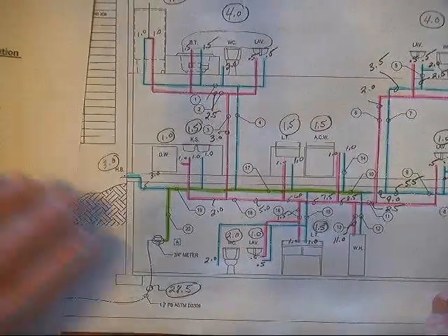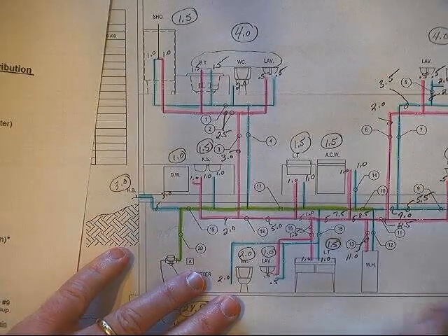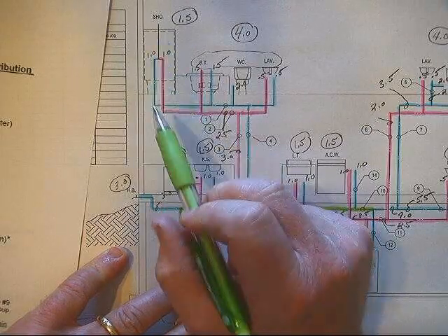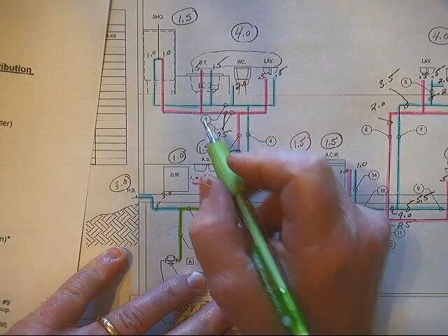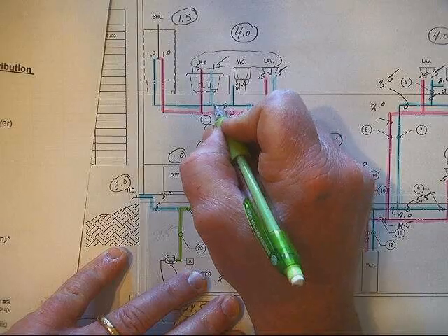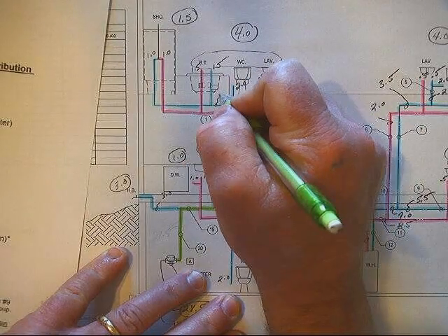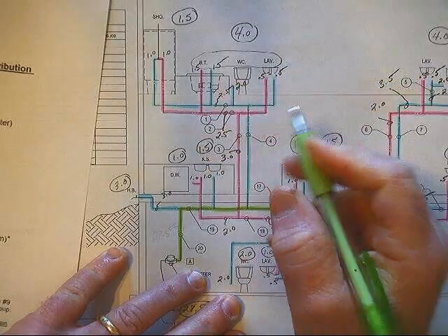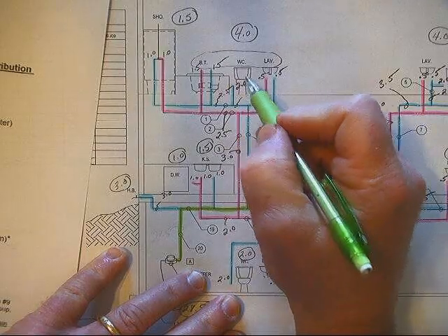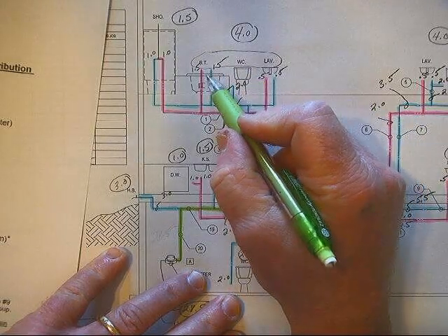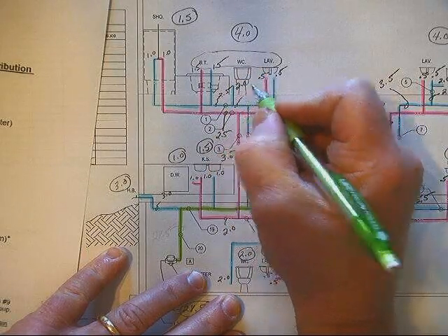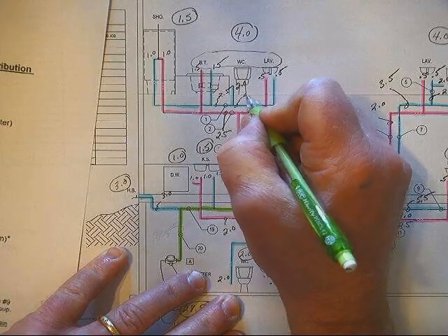We'll move over to the far left side of the drawing. When we get over there, we have upstairs a shower, which was loaded at 1 on the cold side. We had a bathtub that was loaded at 1.5. So this pipe right here would be loaded at 2.5. The next section of pipe now has the water closet, the bathtub, and the shower on there. And so again, we would add the load of the water closet to the other 2 fixtures, and we would be at 4.5.